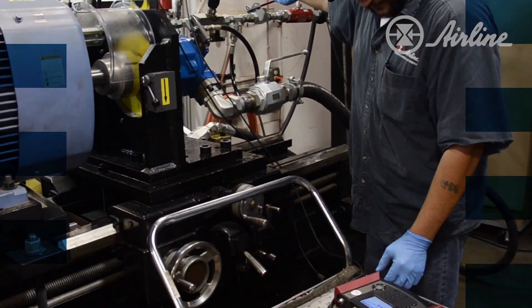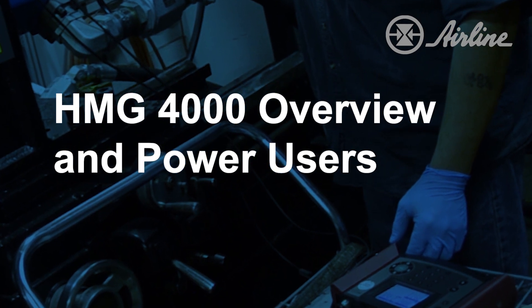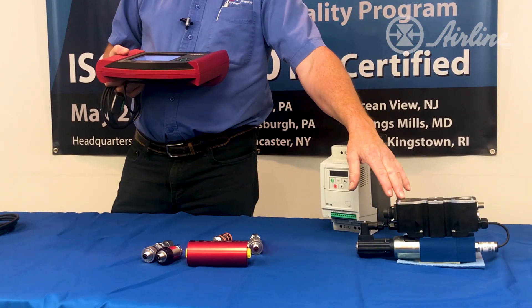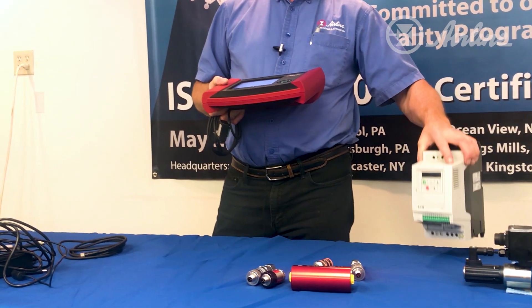One might ask where it could be used or who could use it. It's really a device that can bring in any analog signal — 4 volts, 10 volts, 5 volts, or a current signal 0 to 20 — and you can scale those signals internally to meet any engineering unit you want. It can be flow, CFM, spool position on a proportional valve, or a feedback signal from a VFD that tells you the speed of an electrical motor.